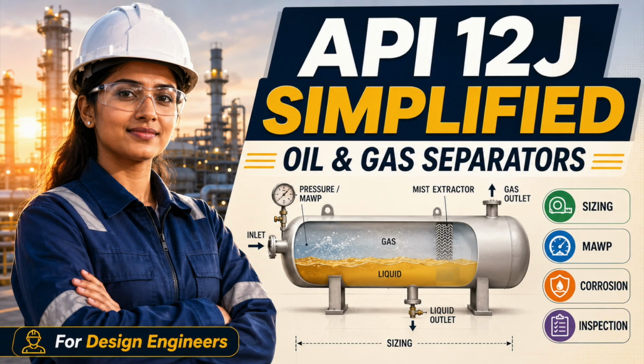The instrument technology, nozzle location, measurement range, and control philosophy must reflect the real fluid. A separator can be generously sized and still fail because the interface measurement is wrong. Poor interface control causes water in oil, oil in produced water, unstable outlet valves, high-level trips, low-level trips, and downstream overload. You cannot solve that by simply increasing vessel volume.